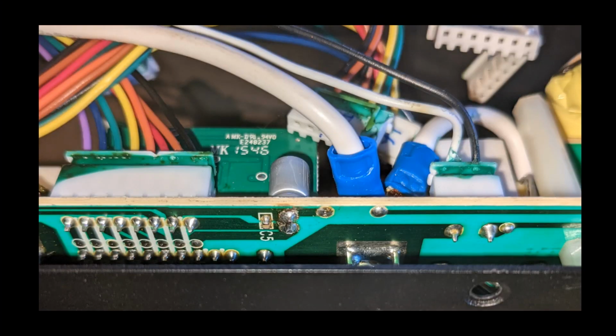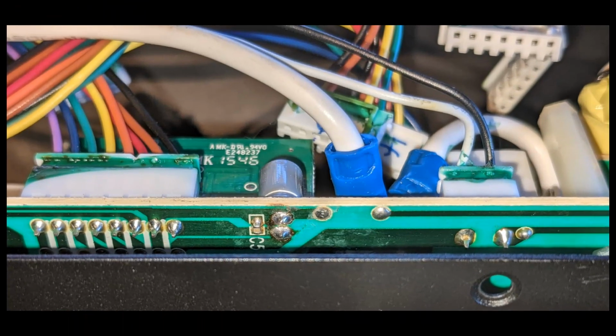A visual inspection revealed a problem. I replaced a capacitor on the power conditioning board. I soldered the cap without removing the board, and there wasn't much space to work. I accidentally created a solder bridge. A rookie mistake. After a little solder wick, the bridge is gone, and hopefully everything will work now.